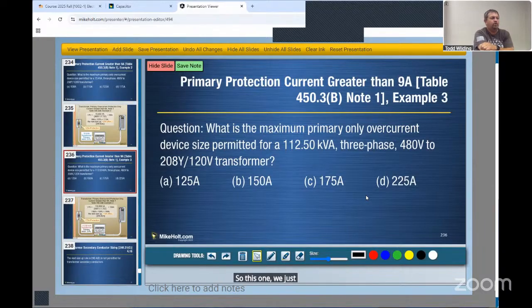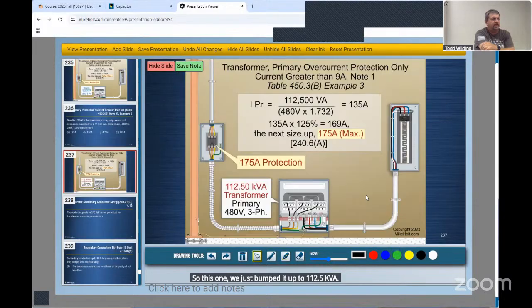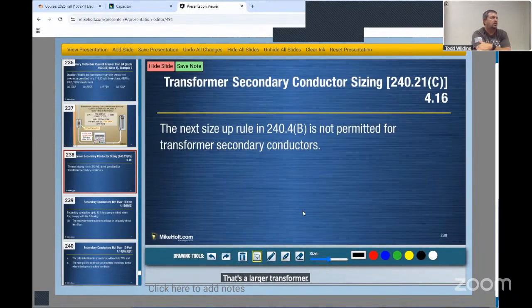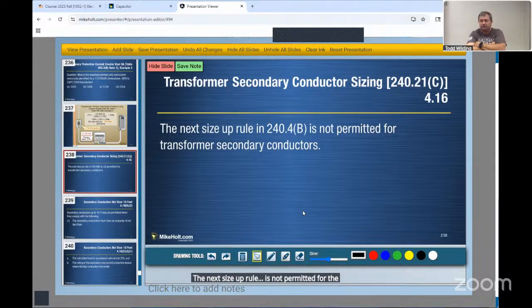So this one, we just bumped it up to 112.5 kVA, 480, 208/120, same thing. 112,500 divided by the 480 times 1.732, I get 135 amps. Times 125%, 169 amps. I'm allowed to go up to the next standard breaker. Does it go 150, 170, 175, or 150, 175? 150, 175, I do believe. That's a larger transformer. The next size up rule is not permitted for the transformer secondary conductors. So those conductors have to carry that full amperage. We'll get into that.